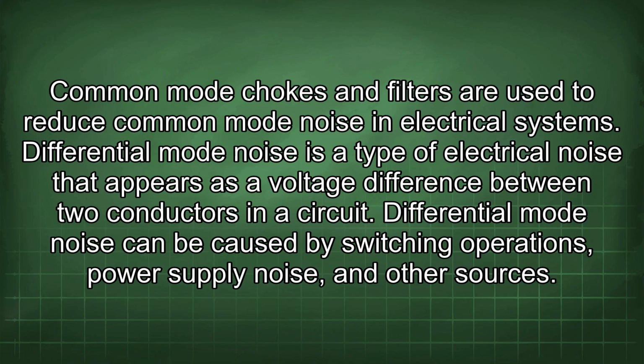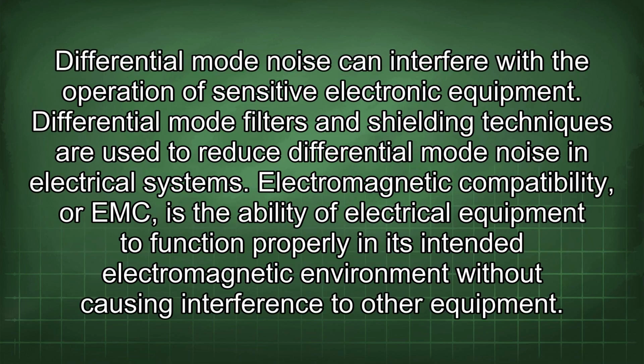Differential mode noise is a type of electrical noise that appears as a voltage difference between two conductors in a circuit. Differential mode noise can be caused by switching operations, power supply noise, and other sources. Differential mode noise can interfere with the operation of sensitive electronic equipment. Differential mode filters and shielding techniques are used to reduce differential mode noise in electrical systems.